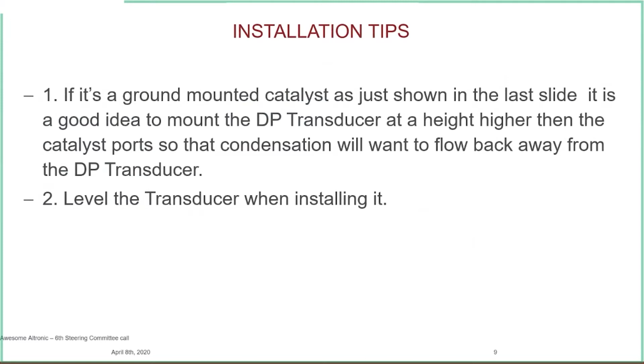So once you get it to that height where you want it, it's a good idea to level the transducer, just to make it work right. Basically inside of it, you've got a diaphragm looking at both the inlet and the outlet of the catalyst, and then it's basically moving capacitance plates, and when those capacitance plates move, they put out a proportional 4-to-20 depending on which way the diaphragm is actually moving. So it's really a good idea to level that transducer when you're installing it.